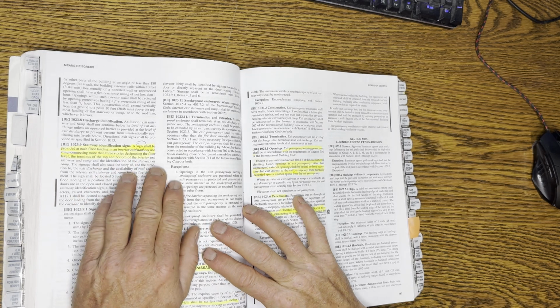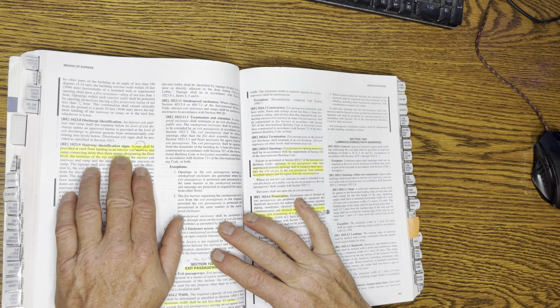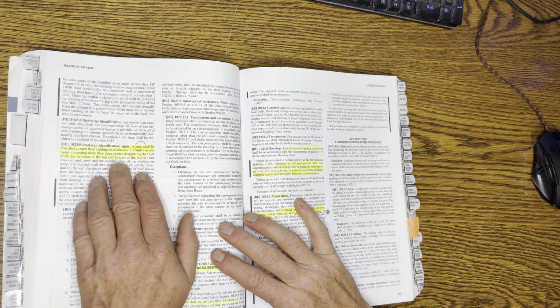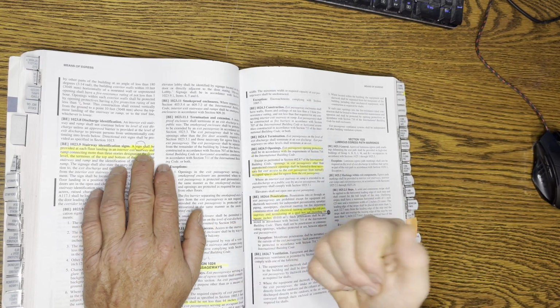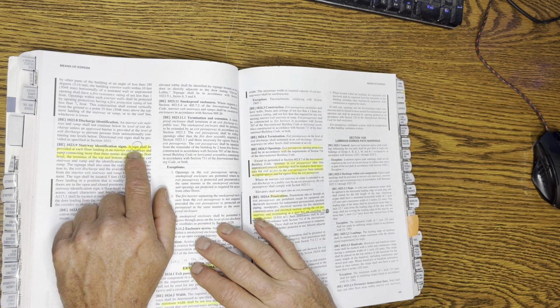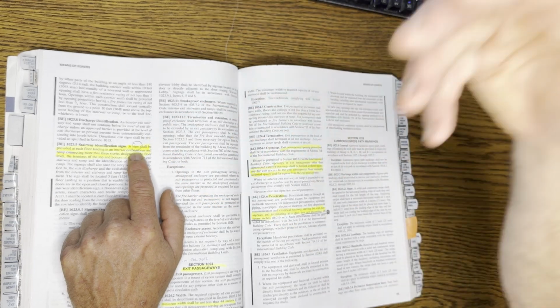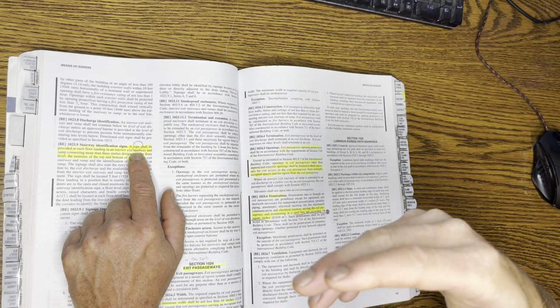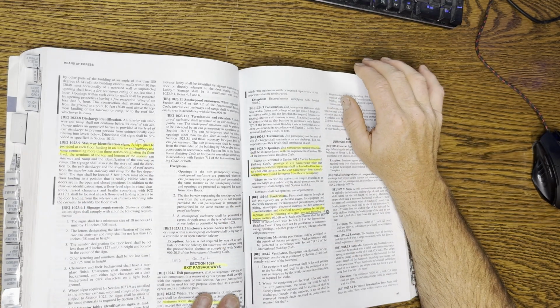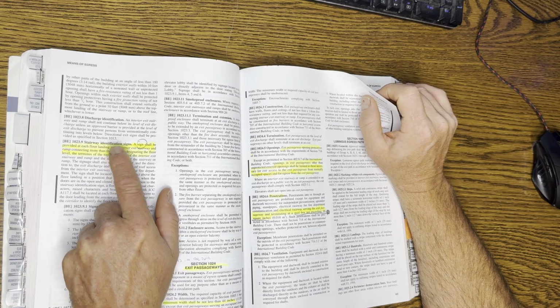Stairway identification sign. If you have multiple stories, you have to assign at each floor landing an interior exit stairway enclosure or ramp. More than 3 stories. The reason for that is they've had a few fires, one particularly, I think it was the MGM Grand, that drove this change back in 1980 in Las Vegas. You need signs on the inside of the stairway enclosure, and you have to have that. So it's a test question. The number is above 3 stories high, so it's right there.